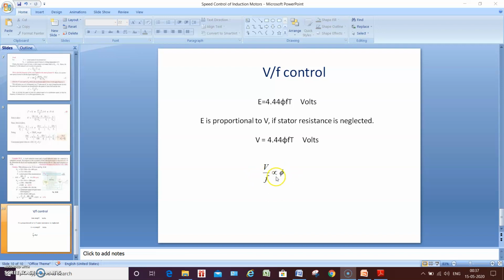So here again, if the flux keeps increasing because of increasing the voltage to control the speed of the motor, the flux will also increase. But actually what will happen is, if the magnetic circuit gets saturated, only the magnetizing current drawn from the source will be increasing, but not the flux, because the flux density will be constant after a certain point.